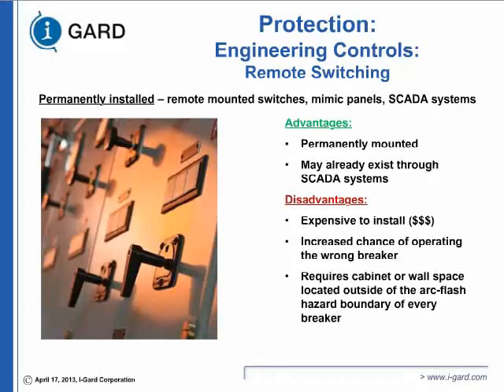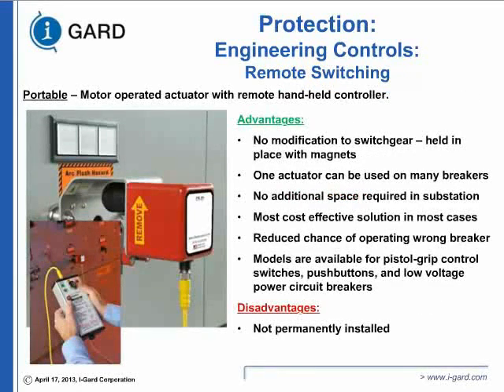You can use a remote actuator, which is magnetically coupled to that device, and you go 20 feet or 25 feet, which comes in different lengths. You can operate it remotely. Distance is your friend on arc flash. The further you go, the better off you are. A disadvantage of this system might be that they're not permanently installed, so they depend on a human to operate and install them. If you're interested in your safety, you'll probably train your people to do that.